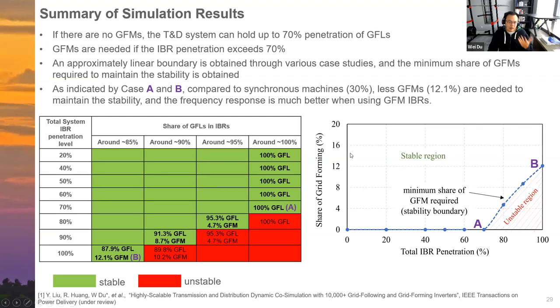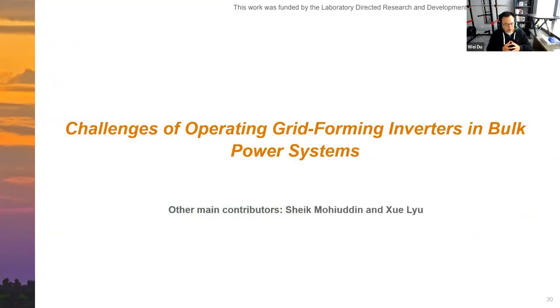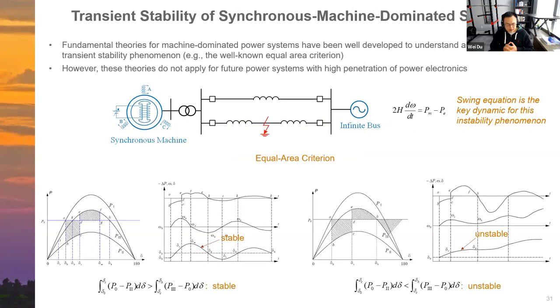So this is a very active work, and there is still a lot of work going on in this research area. In the first three sections, I talked about a lot of good things about grid forming inverters. Grid forming inverters can survive overload events and can improve a system's primary frequency response. But if grid forming inverters were that perfect, we wouldn't need to do research anymore. In reality, there are still a lot of challenges for grid forming inverters that need to be further studied. One of the critical things is the fault ride through behavior and the transient stability of grid forming inverters.